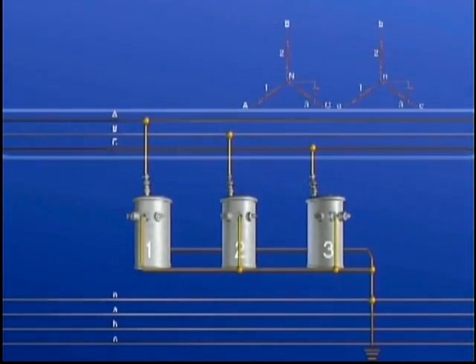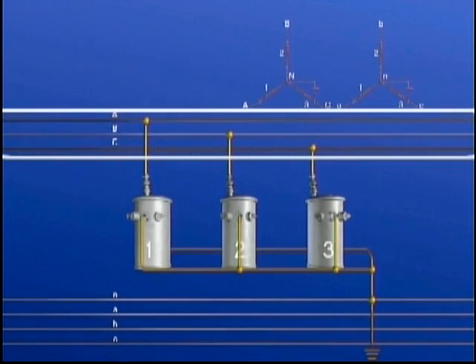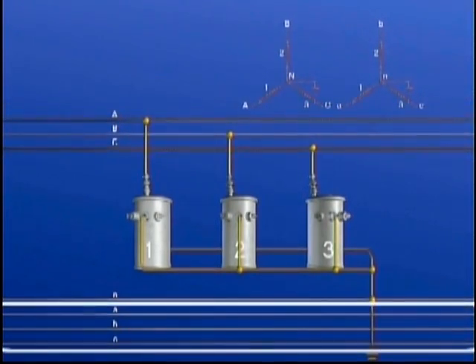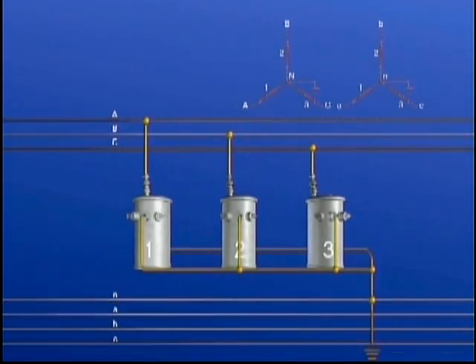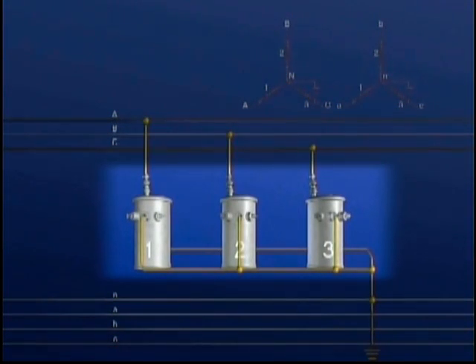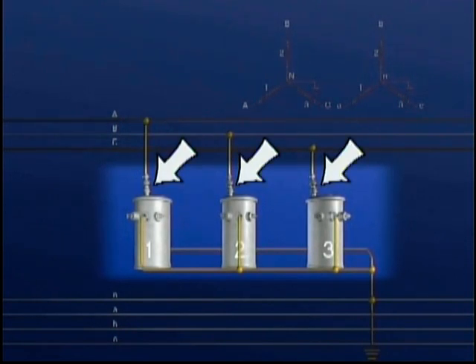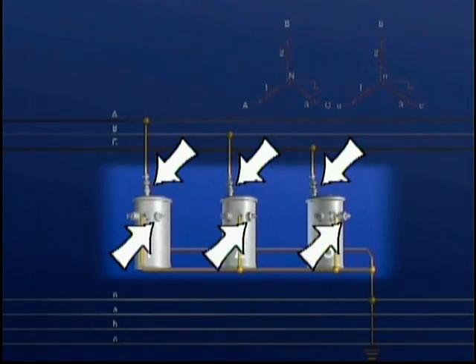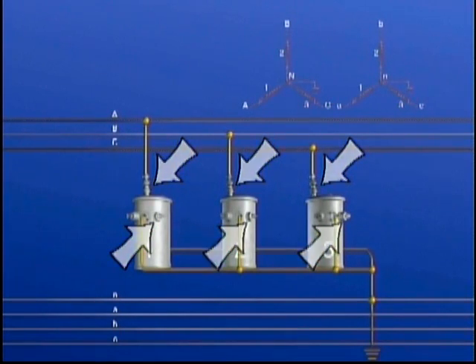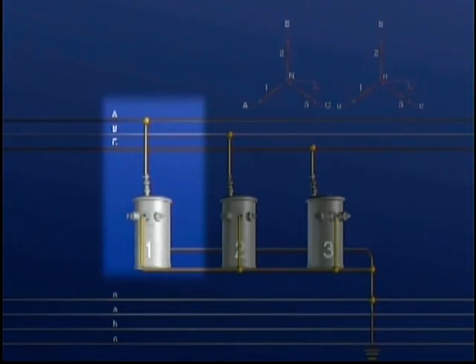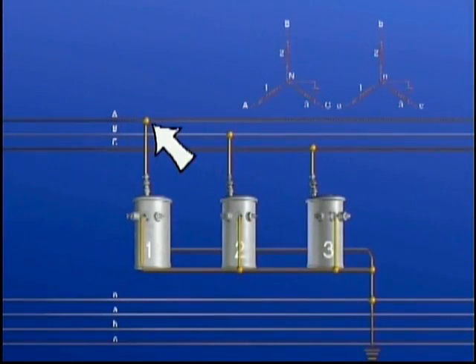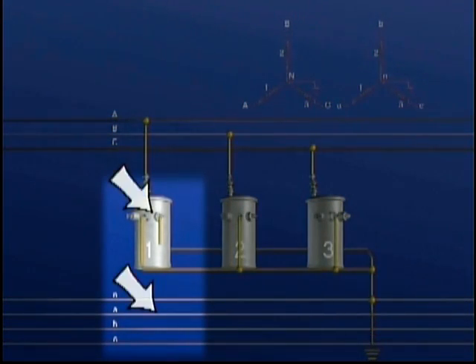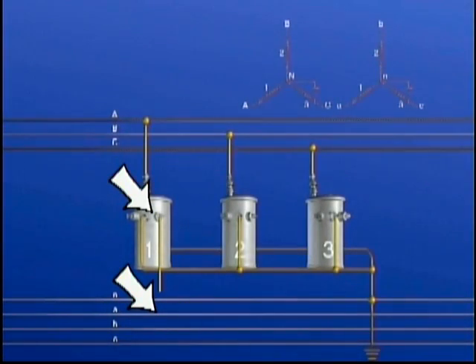In this example, we'll designate the primary phases on this illustration A, B, and C. We'll designate the secondary lines beneath the grounded neutral, secondary A, secondary B, and secondary C. We'll establish a relationship between the primary and secondary windings that has 0 degrees angular displacement. Whatever primary phase the H1 end of a primary winding is connected to, the X1 end of the secondary winding should be connected to the corresponding secondary line. In this case, the H1 bushing on transformer number 1 is connected to phase A. Therefore, the X1 bushing on transformer number 1 will be connected to secondary line A.